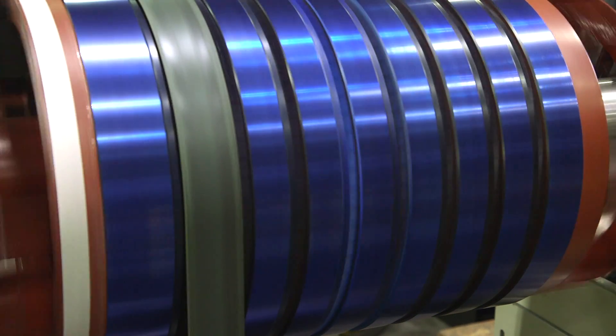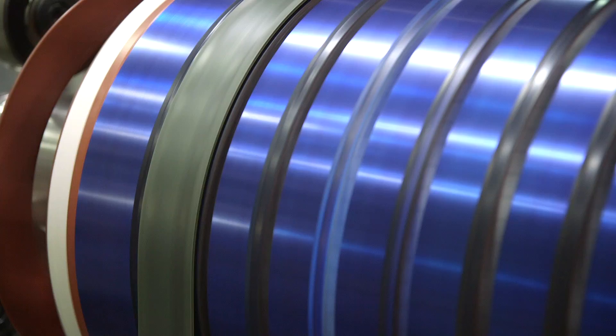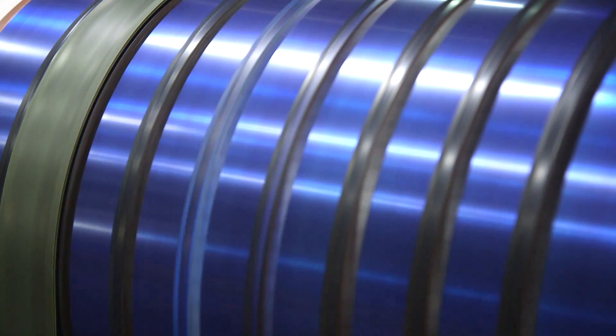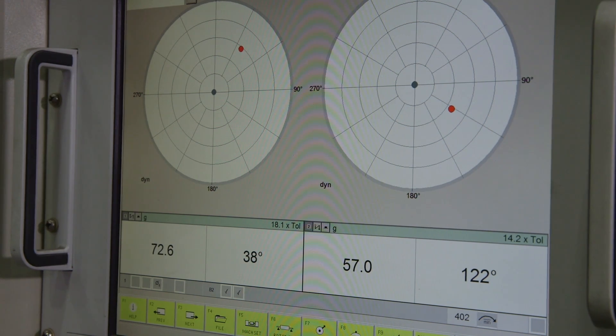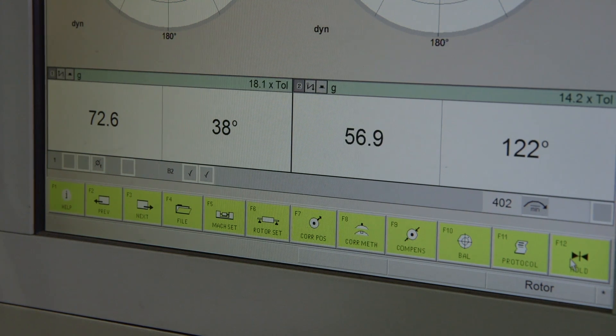For example, on your Ferrari that you may have in your garage, the tires are balanced to say a quality grade of G40. This particular instrument, we balance our units down to a G0.4. G0 of course is perfect — we can't achieve that unless we're in outer space — but that is really, really precise.